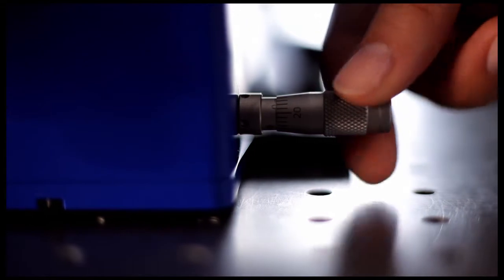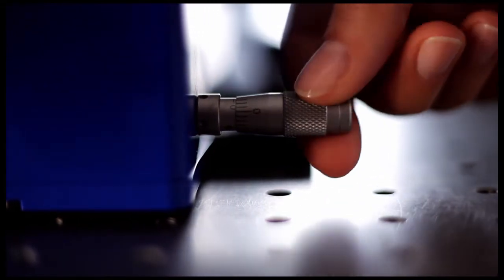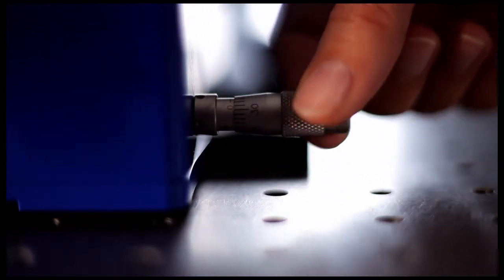When you align the incoming beam with PulseCheck, you use collinear mode to overlap the output beams, so you only needed to focus one beam in the crosshair. But this produces a lot of interference. To change to non-collinear mode, you simply need to turn a single micrometer screw on PulseCheck.